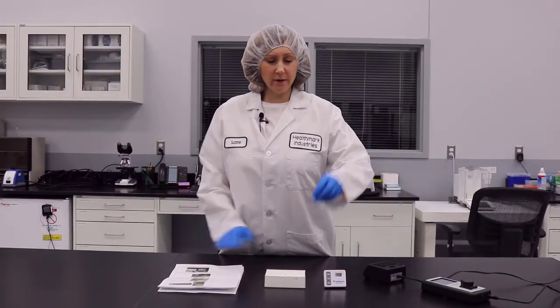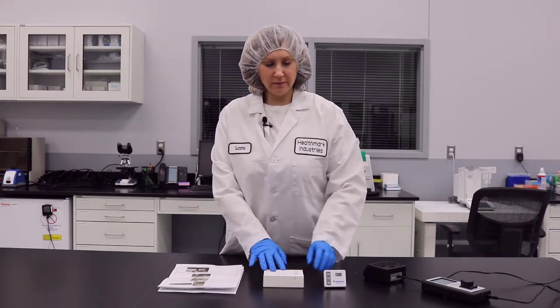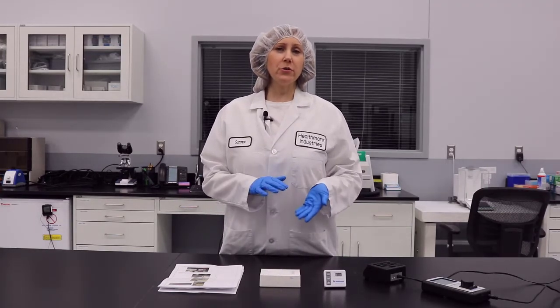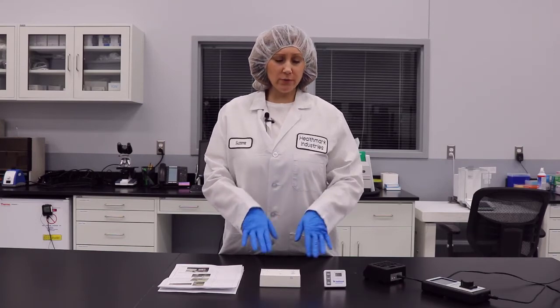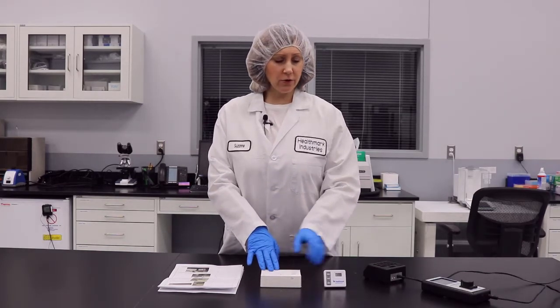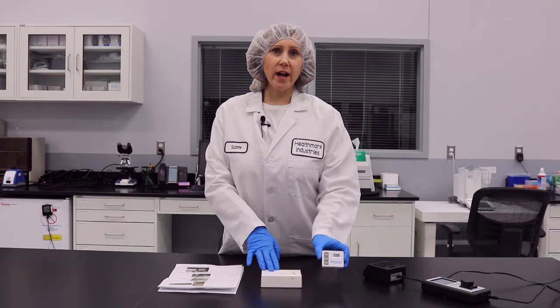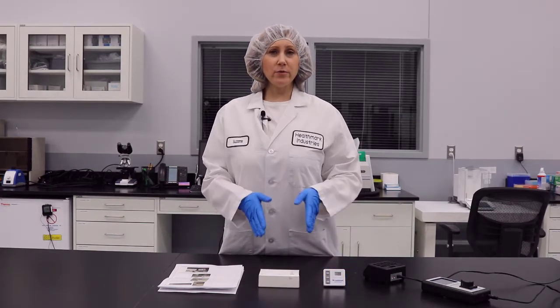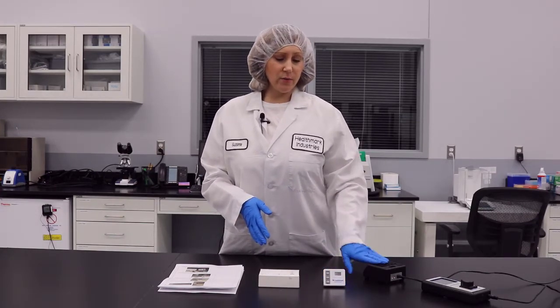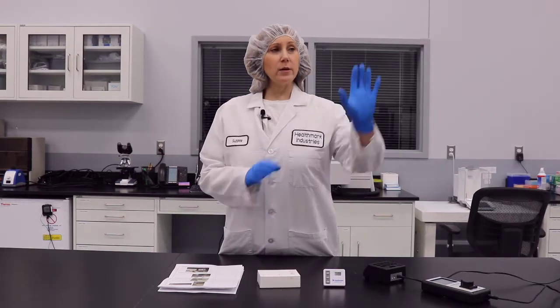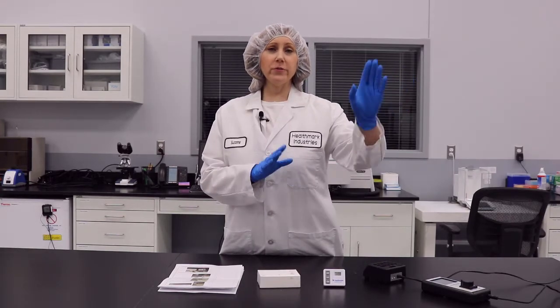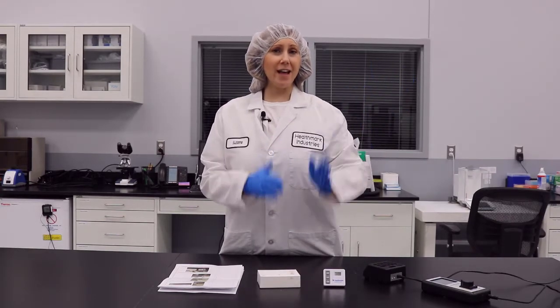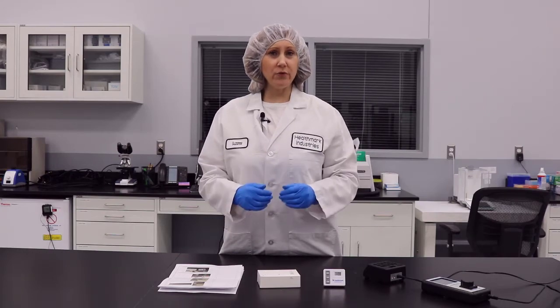Okay, now that the incubation period has passed, take the cuvette out of the incubator and place it into the cuvette holder. You have two ways of cooling the cuvette down, either by room temperature or by refrigeration. So by room temperature, keep it in the cuvette holder. Set your timer for 1 hour to let it cool down. The other option is refrigeration: take it out of the incubator, place it in the cuvette holder, immediately place it into the refrigerator for 15 minutes, and keep it in there for exactly 15 minutes. Remove it and proceed to the next steps.